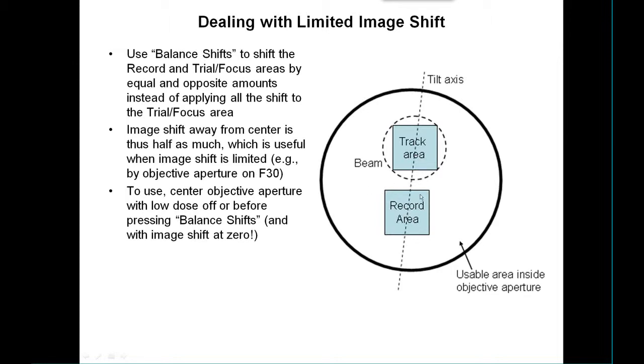To use this, you need to make sure the objective aperture is centered and the image shift is zero before you either activate low dose or press the balance shift button to switch to this mode.